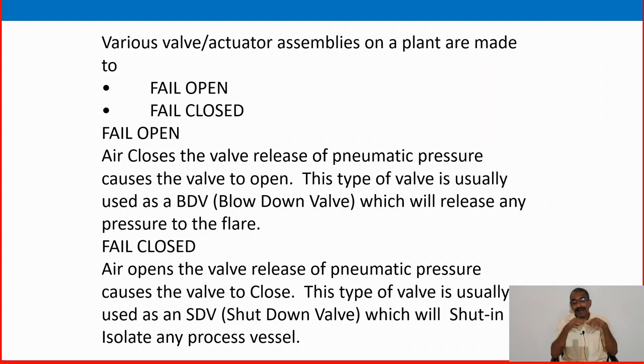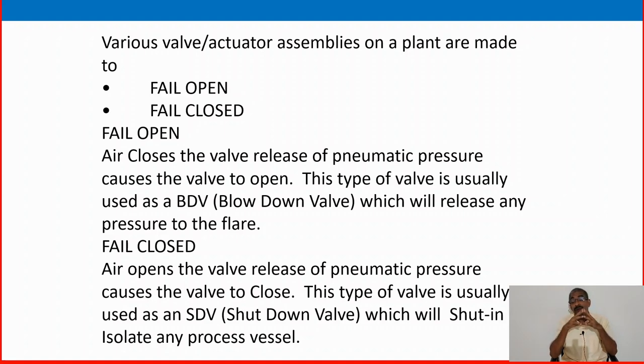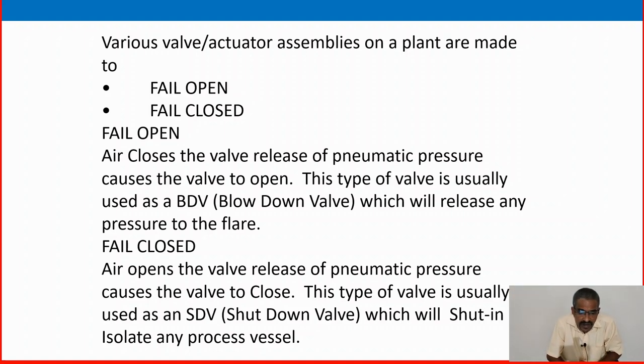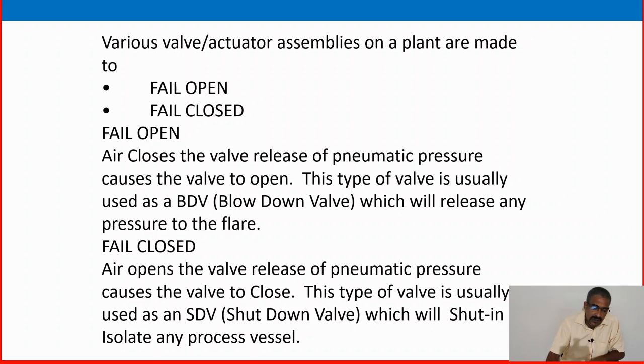The BDV works in the downstream or discharge area of a gas line to release the separator inside pressure or equipment inside pressure — the BDV is a fail-to-open valve working as a blow down valve, releasing gas pressure to flare or any other safe location. Fail closed: air opens the valve; release of pneumatic pressure causes the valve to close. This type is called SDV — shut down valve — which will shut in or isolate any process vessel.